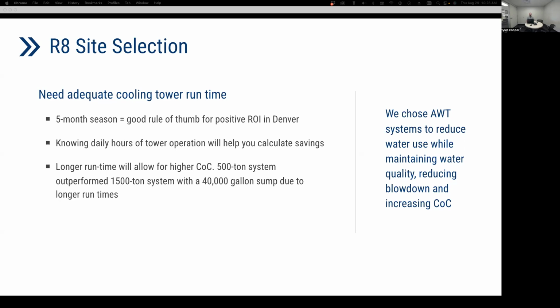So we just want to focus on what we've learned as a region and what we see as best practices moving forward. One of the things that's been consistent through this process is the need for adequate cooling tower runtime. With our installations here in Denver, we have generally a 5-month cooling season, which still provides a good positive ROI for us. I think David noted that the average water cost nationally is a little over $18 per 1,000 gallons. Here in Denver, we see closer to about $7 per 1,000 gallons, and we're still seeing that ROI with these technologies. So as you're going through site selection, knowing those daily hours of operation for the tower helps you calculate savings. One of the good indicators of performance is cycles of concentration. Generally, if we're around 3 cycles of concentration or thereabouts, we know there's a good opportunity for savings and improvement in those towers.